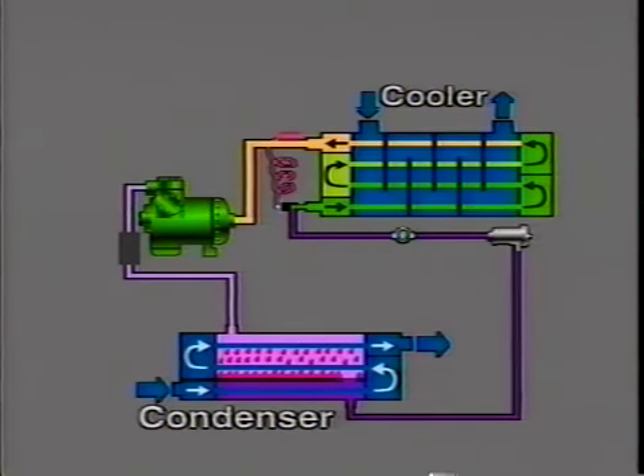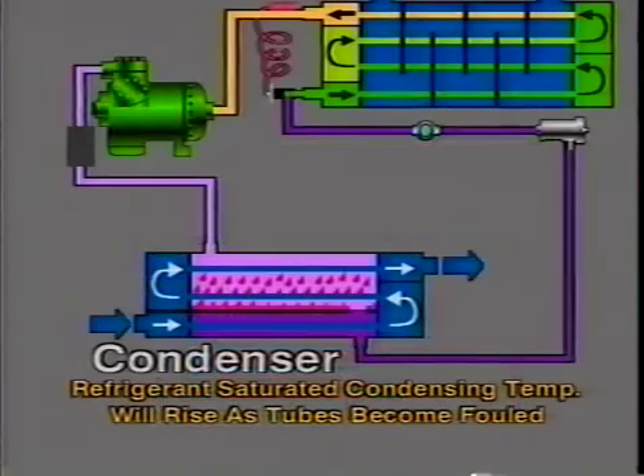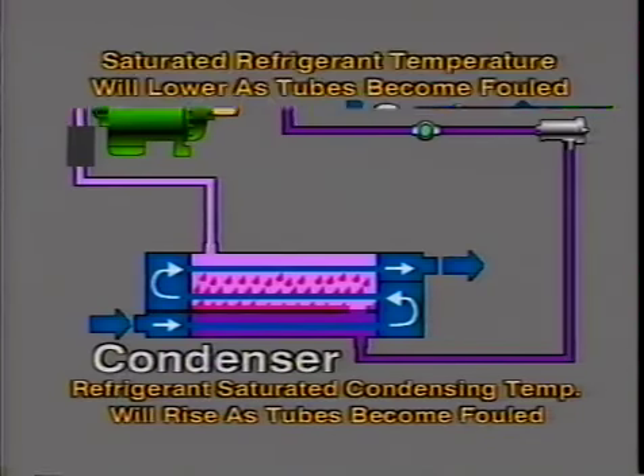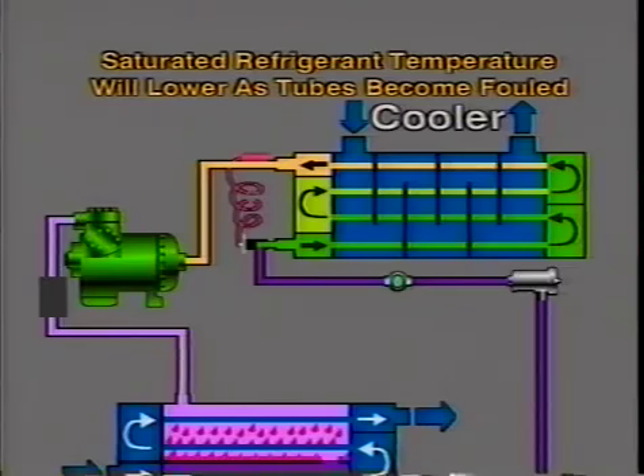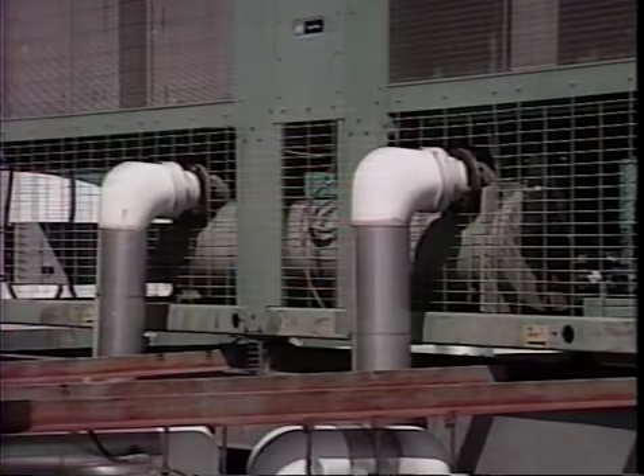Whenever water is involved, heat transfer surfaces tend to become fouled, and there is a correlation between fouling of waterside surfaces and the loss of heat transfer. The refrigerant saturated condensing temperature will rise as the condenser tubes become scaled. In the cooler, the saturated temperature will become lower as the cooler tubes become fouled and the heat of the secondary refrigerant, water, brine, or glycol, takes longer to reach the primary refrigerant. A scale buildup of just 1/1000th of an inch of waterside fouling can cause an efficiency drop in heat transfer between the primary and secondary refrigerant.